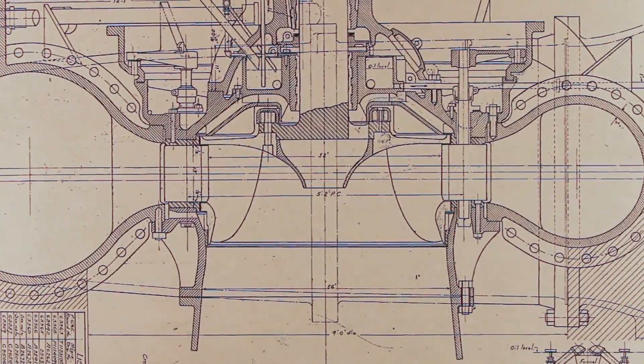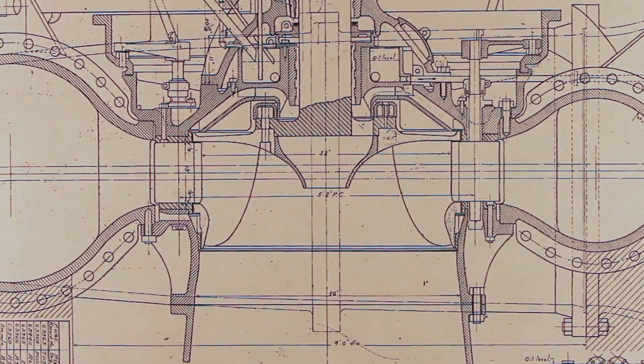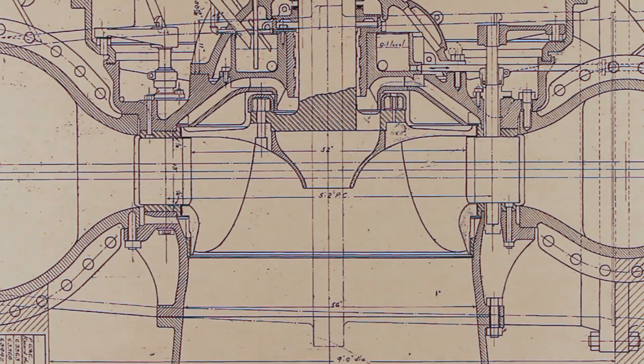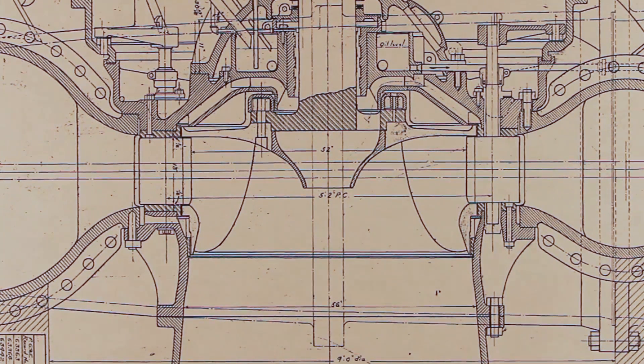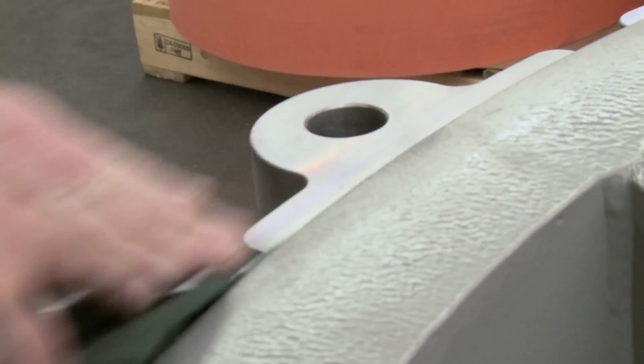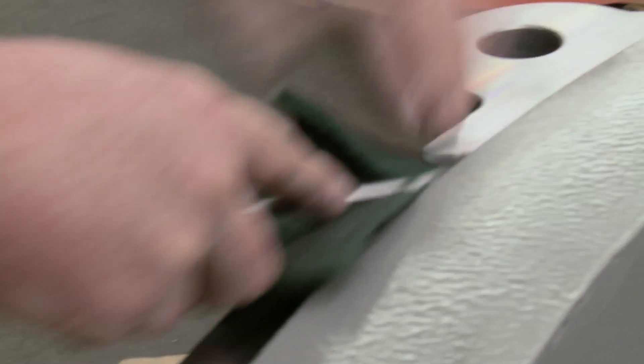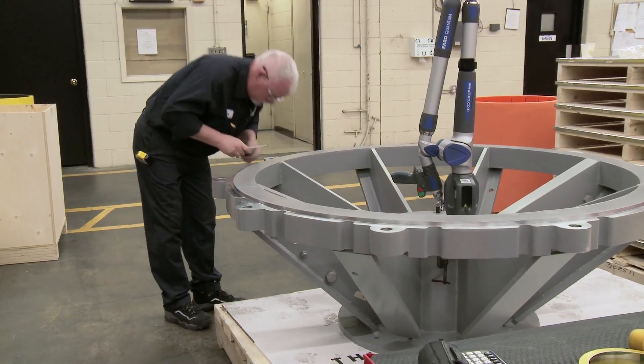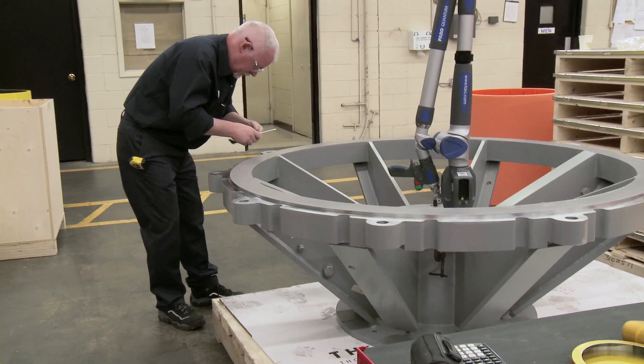The lower main guide bearing ensures that the shaft supporting the turbine below runs true and positions the runner in the center of the scroll case. The second oil-lubricated guide bearing is typically located within the thrust bearing assembly, above the generator, and poses little risk of leakage beyond the powerhouse.